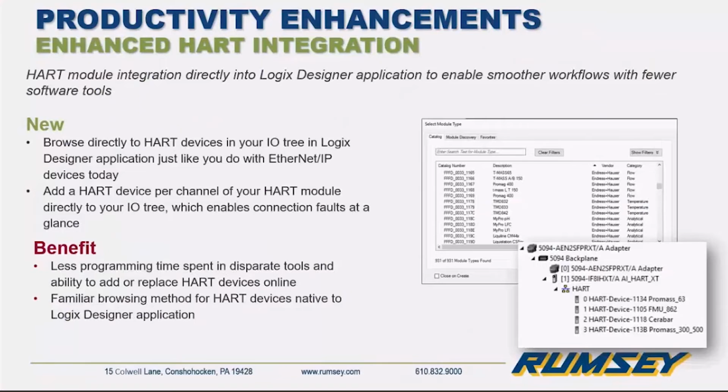This was actually partially brought out in version 32, but we have it new. Bring it into 33, enhanced HART integration. So with our new IO platform and with some new features, basically you can go right through the software, right out and configure your HART device. You don't need any add-ins, plus programming. You don't need any separate tools. So anybody using smart HART devices, this makes it a lot easier to integrate into the system. Everything's kept in one place. Nothing additional needed.